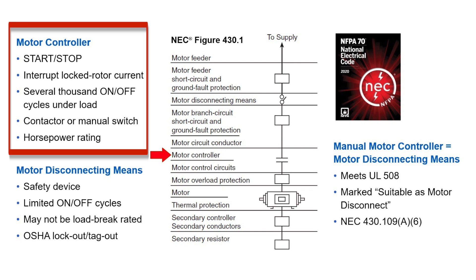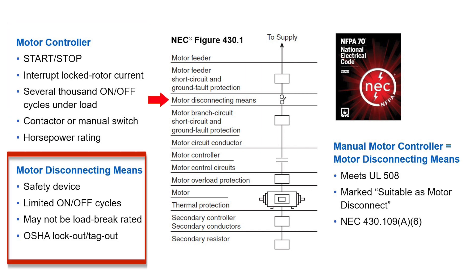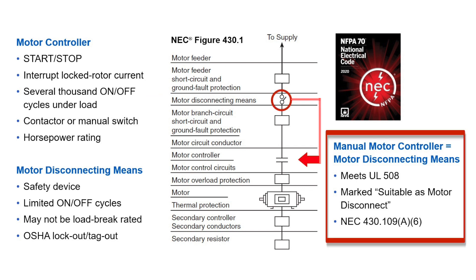In addition to its current rating, a motor controller will also have a horsepower rating. The motor disconnecting means is more of a safety device, primarily used to de-energize the circuit during service. It's designed for limited on and off cycles and must have a provision for being locked in the off position to ensure the circuit cannot be re-energized. A manual motor controller can also serve as the motor disconnecting means if it meets certain requirements of the UL 508 standard and is marked suitable as motor disconnect — in other words, the controller and the disconnect can be the same piece of equipment.